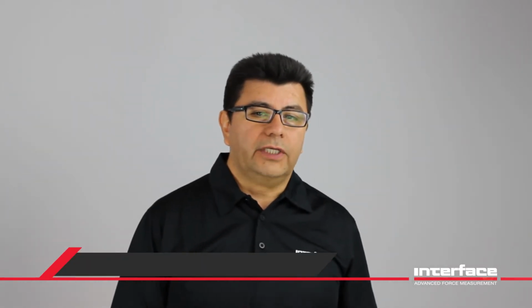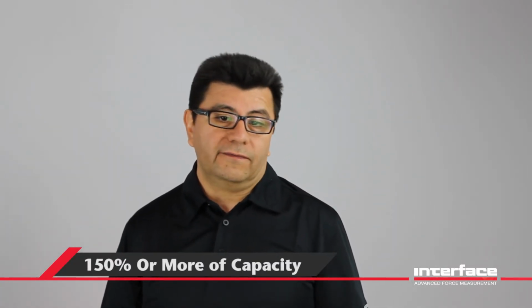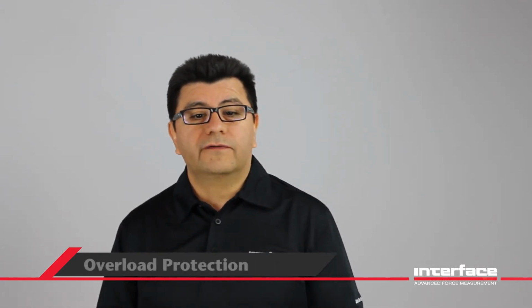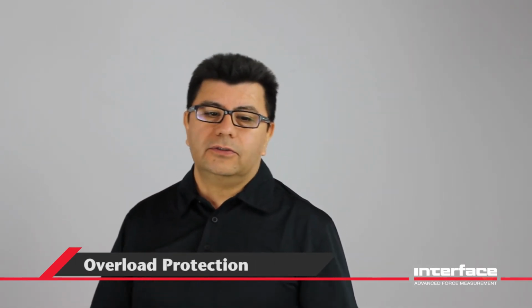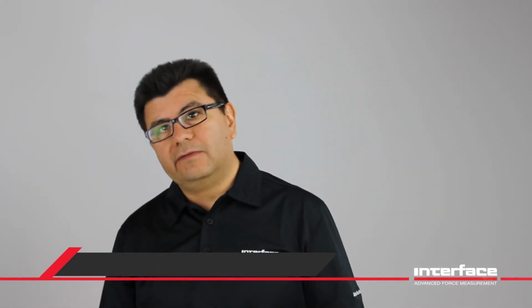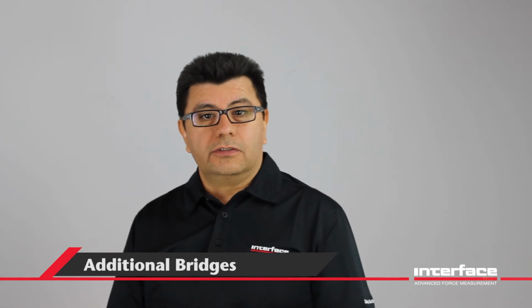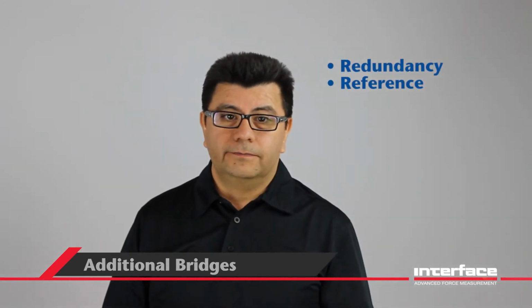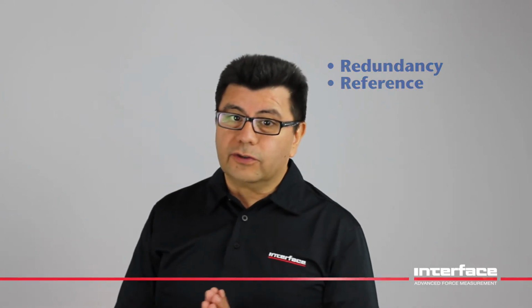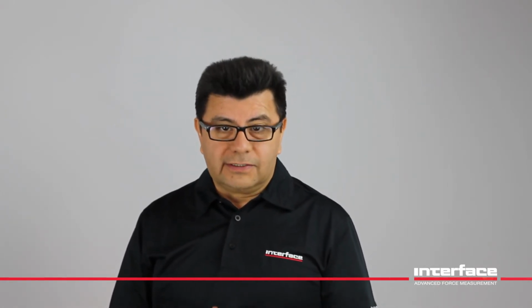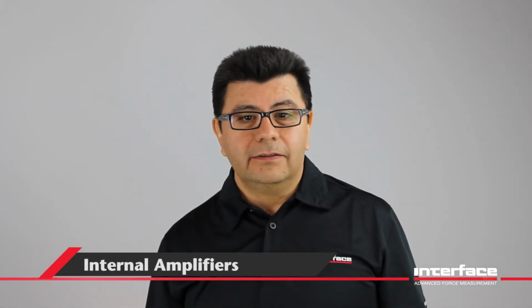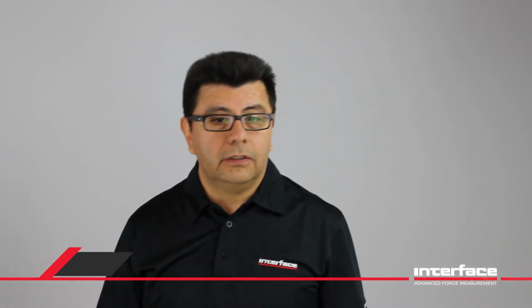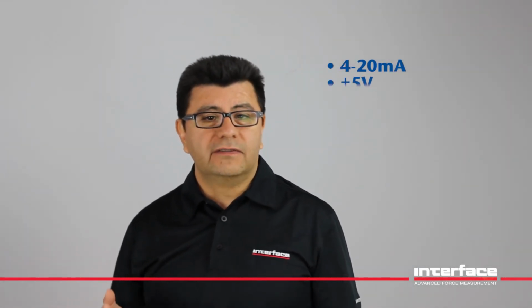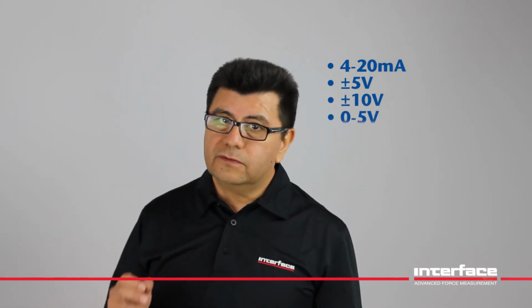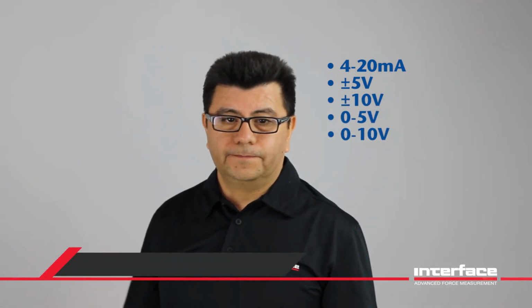All Interface load cells are rated at 150% or more of capacity. If you need more, we offer overload protection, a mechanical solution that protects a load cell from exceeding forces. Second and third bridges are used for redundancy or reference. These are particularly useful in ensuring a working load cell for extended period testing. An internal amplifier is used to modify the signal to the type of output required, including 4 to 20 milliamps, plus or minus 5 volts, plus or minus 10 volts, 0 to 5 volts, and 0 to 10 volts.